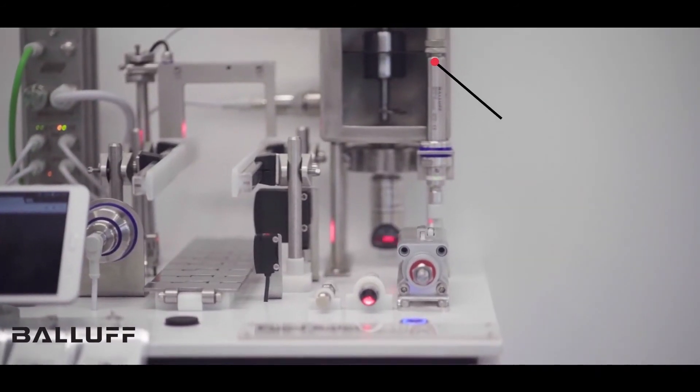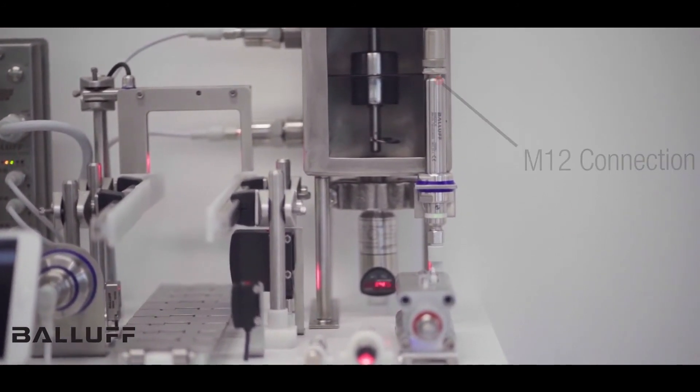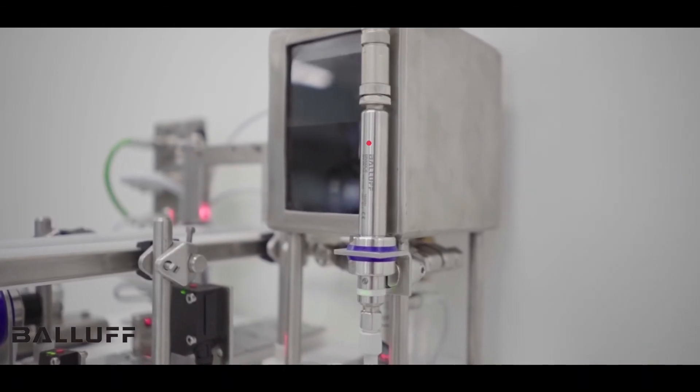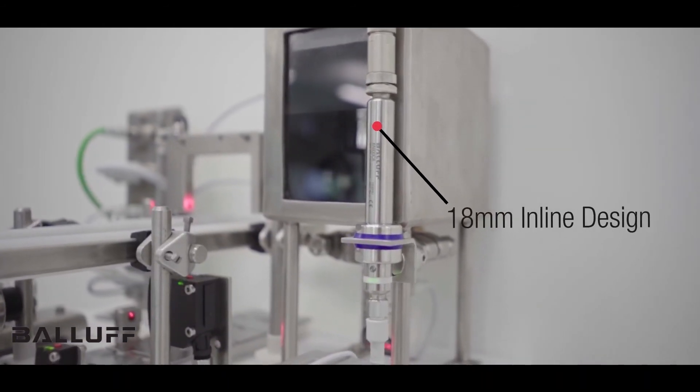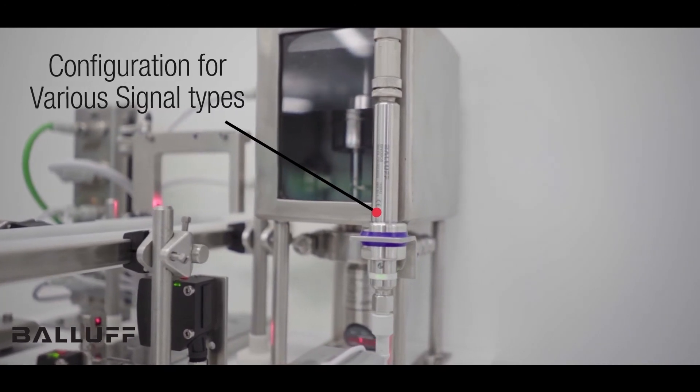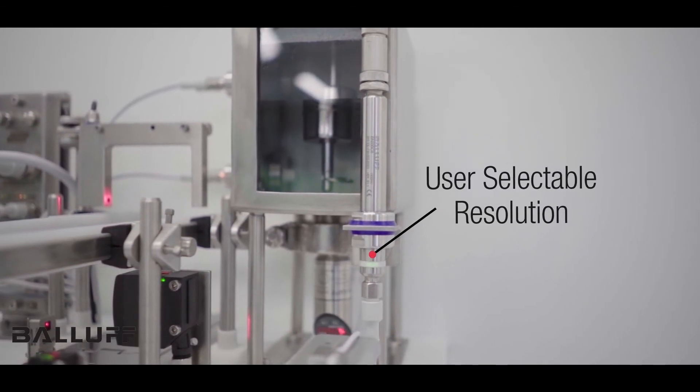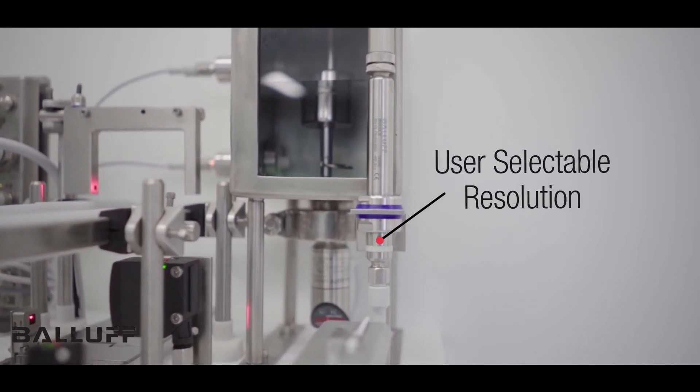Each uses a standard M12 connection and supports two, three, and four wire devices. They feature an 18mm inline design allowing for easy installation and can be fully configured for various signal types. They also have a user selectable resolution from 10 to 16 bits for the digital values.